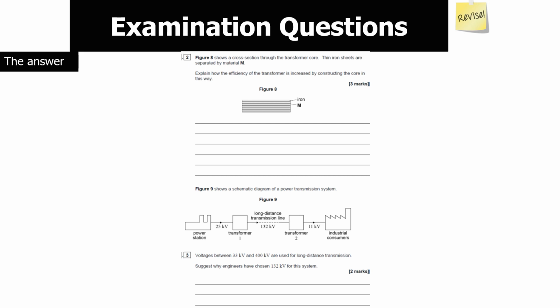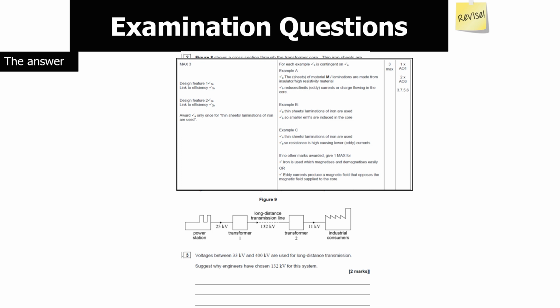Right, so what you should understand is when you see an M in this particular transformer, M is an insulator. When we cover a material in insulation, that is called lamination. So these laminations or laminates are made from an insulator or high resistivity material. Why do we have this? Well, this reduces the impact of eddy currents in the transformer because with such high resistance, you won't get a high current forming.